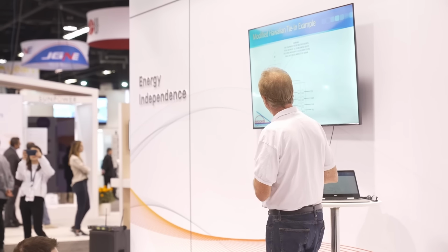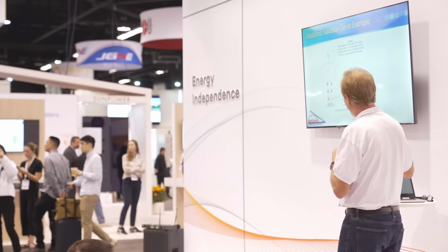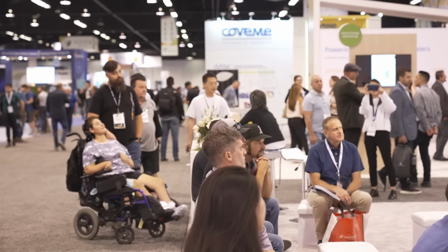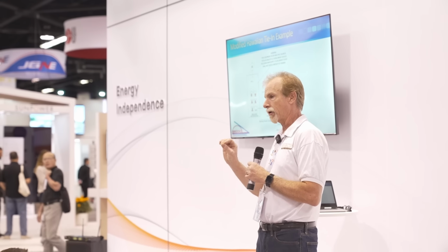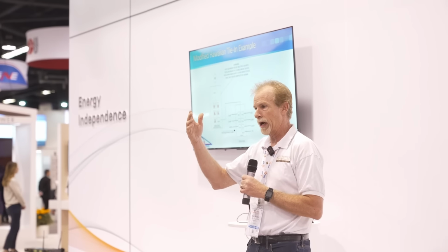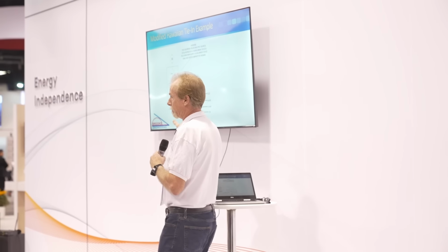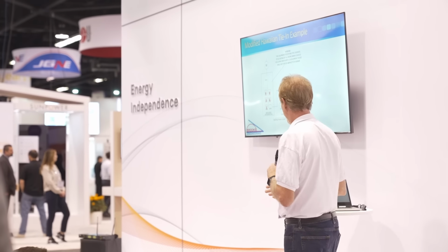So anyway, what this does is this gets us away from that main service disconnect. Keep the main service disconnect, move away from that. And now we put a 100 amp breaker in there. Now that we have the 100 amp breaker, we can do anything we want downstream of that. The only thing limiting us is the 100 amp circuit, but that's already limiting us, right? Because we have a 100 amp service disconnecting means, so by its very definition, we can never shove more than 100 amps back through that breaker anyway, whether you do a supply side connection or not. It makes no difference, it's the same thing.